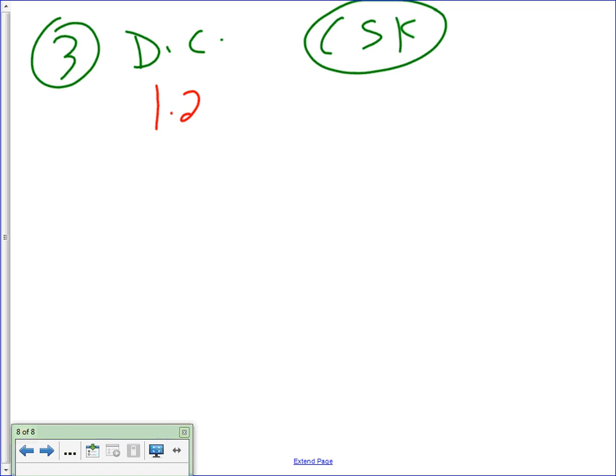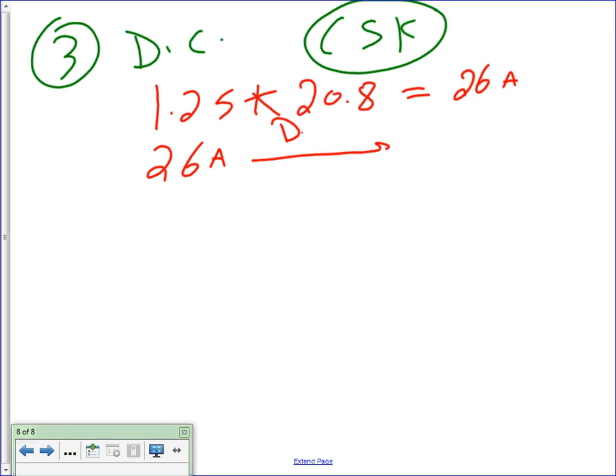So I would use 1.25 multiplied by, what was the full load current again? 20.8. Thank you. And that would give me, we did the math on that one. What was the math? For the conductor, we didn't. What is it? 26 amps. 26 amps. Okay? Then I take 26 amps to the table 240.6, and that would go up to 30 amp. So I have a 30 amp disconnect. So exactly like the one on the wall. Throw a 30 amp disconnect right next to it. 2-pole. 30 amp 2-pole. Any questions, guys?